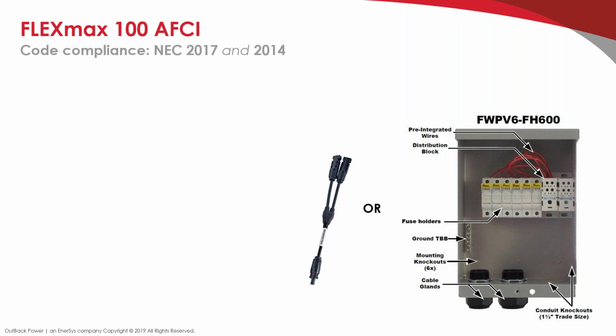We are basically recommending NEC 2017 compliance, and the general consensus is that NEC 2017 inherently complies with NEC 2014. So if you're in a region where NEC 2014 is still standard, because NEC 2017 is more recent and more stringent in a way, by complying with NEC 2017, you would be complying with NEC 2014 automatically, as well as NEC 2017.